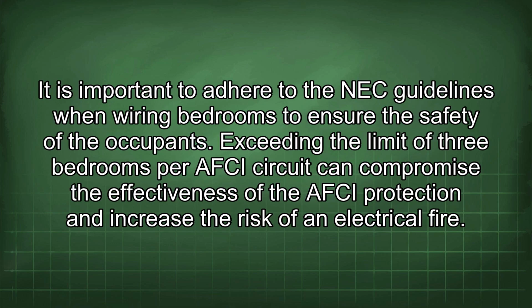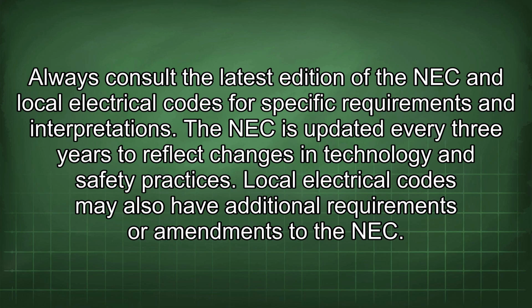It is important to adhere to the NEC guidelines when wiring bedrooms to ensure the safety of the occupants. Exceeding the limit of 3 bedrooms per AFCI circuit can compromise the effectiveness of the AFCI protection and increase the risk of an electrical fire. Always consult the latest edition of the NEC and local electrical codes for specific requirements and interpretations. The NEC is updated every 3 years to reflect changes in technology and safety practices. Local electrical codes may also have additional requirements or amendments to the NEC.